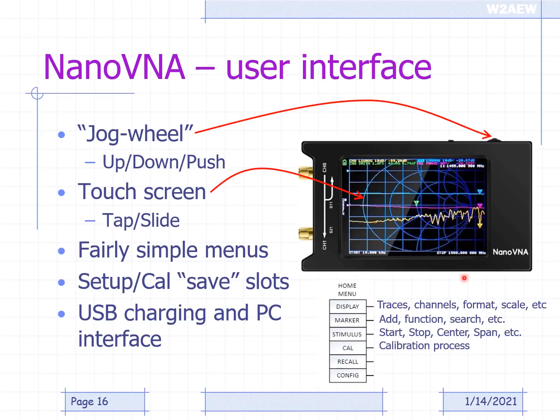A couple more details on the calibration. Most of the VNAs are just 101 points per sweep. So what that means is a wide frequency range is going to have a fairly coarse spacing between the calibrated points. But if you calibrate over the frequency range you're measuring, that's fine. But if you later change the frequency range, the VNA will try to interpolate between those calibrated points. But you don't want to calibrate over a gigahertz and then measure over 1 megahertz, because you might not even have 1 point sitting inside that measurement range. So it's always a good idea to calibrate over your frequency range.